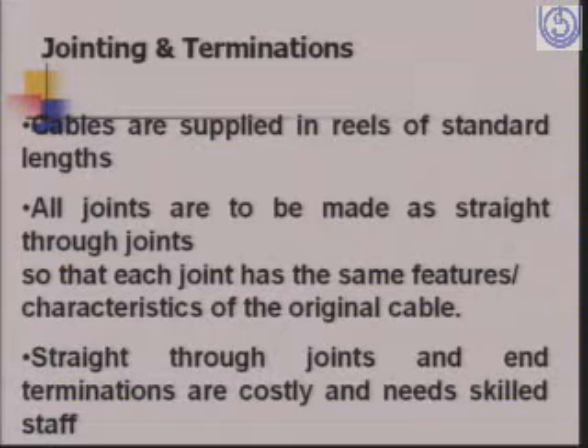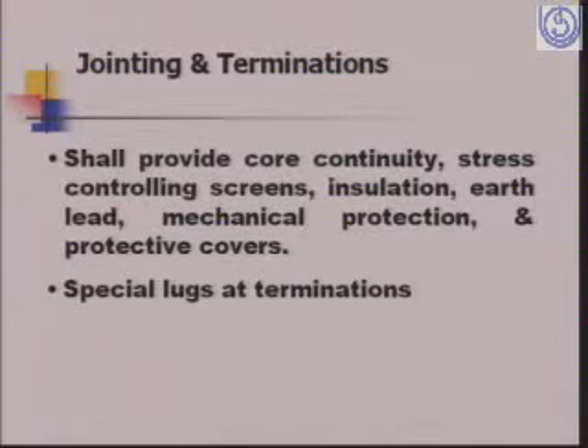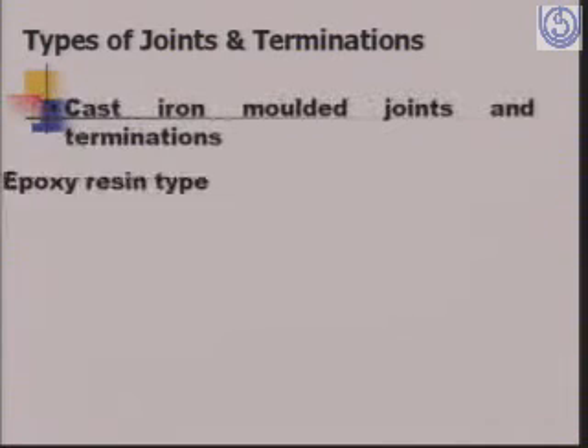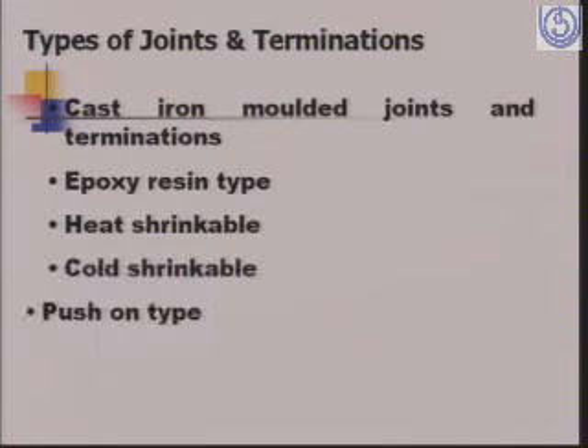Then the cable jointings and terminations in case of cables are very important. The cables are supplied in reels of standard lengths, and joints have to be made, and all joints are to be made as straight through joints, so that each joint has the same features and characteristics of the original cable. Straight through joints and end terminations are costly, and they need skilled staff. They shall provide core continuity, stress controlling screens, insulation, earth lead, mechanical protection, and protective covers. So special lugs have to be used at terminations, and we have various types of joints and terminations.